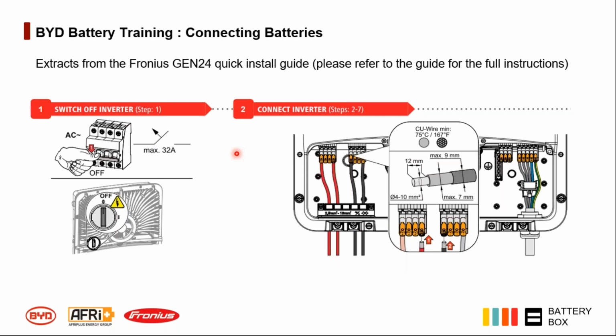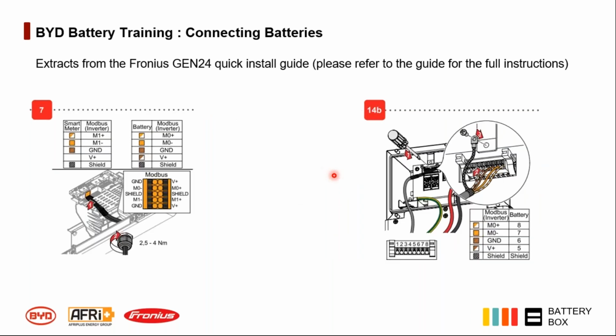And here's just some quick extracts of the quick install guide. Fronius has got a very easy to read quick install guide on how to connect the inverter to the batteries. Always make sure, please, that your inverter is off when you are connecting your batteries. And then here we've got your connections of your battery cables. Always please make sure that your battery cables are connected in the correct connector. And here we've got the communications cables. It's always important to make sure your communications are in order, otherwise the system will not turn on. Here we've got the Fronius side, and on the BYD side, we do prefer using the wire connector rather than the RJ45 connectors. It seems to work far more reliably.